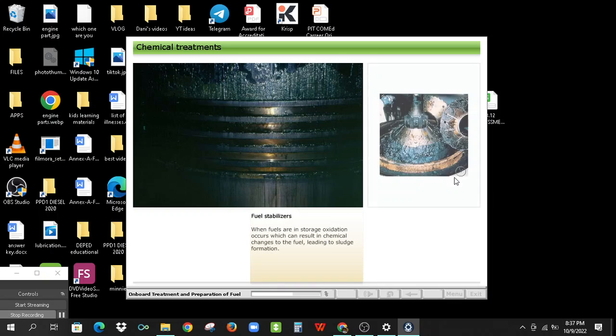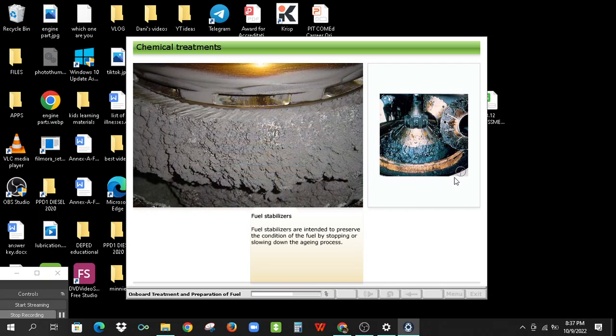When fuels are in storage, oxidation occurs, which can result in chemical changes to the fuel, leading to sludge formation. The chemical changes can also affect the combustion performance of the fuel. Fuel stabilizers are intended to preserve the condition of the fuel by stopping or slowing down the aging process. If the stabilizer is effective, then the fuel should burn more cleanly and emissions should be reduced.